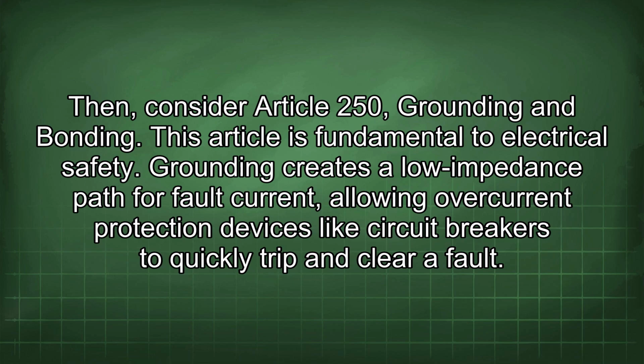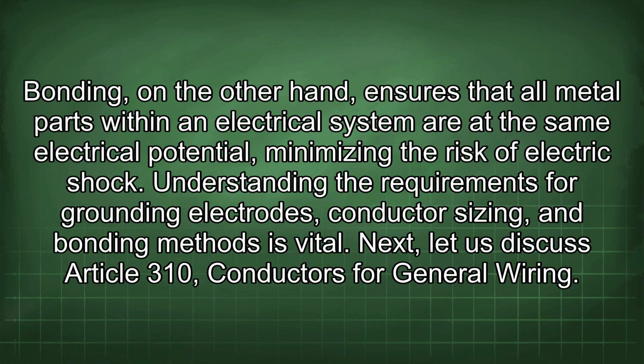Then consider Article 250, grounding and bonding. This article is fundamental to electrical safety. Grounding creates a low impedance path for fault current, allowing overcurrent protection devices like circuit breakers to quickly trip and clear a fault. Bonding, on the other hand, ensures that all metal parts within an electrical system are at the same electrical potential, minimizing the risk of electric shock. Understanding the requirements for grounding electrodes, conductor sizing, and bonding methods is vital.